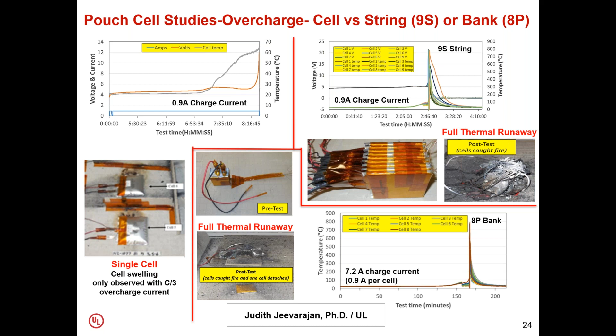But when we overcharged it with a C/3 rate current, which was 0.9 amps, we found that the cells just swelled. So we took that same equivalent current and tested it with a string of 9 cells and a bank of 8 cells. In both cases, all the cells went into catastrophic thermal runaway with a big fire, and post-test, there was no cell left behind.